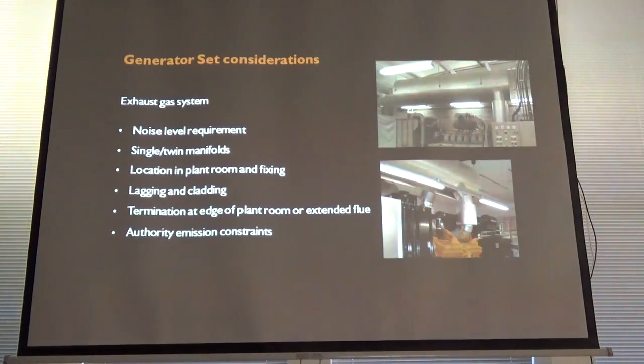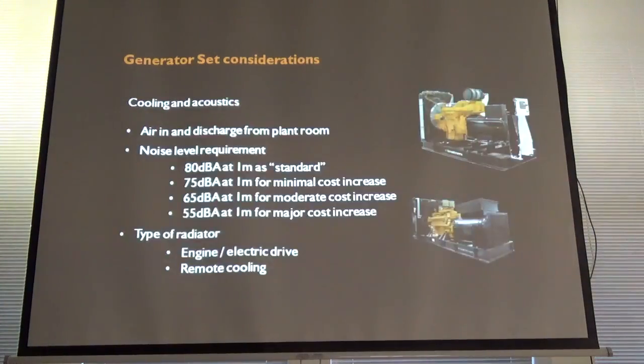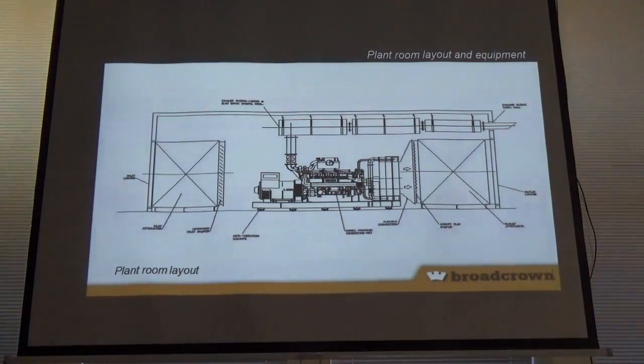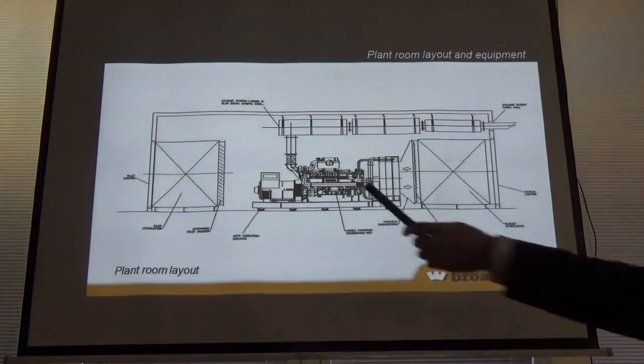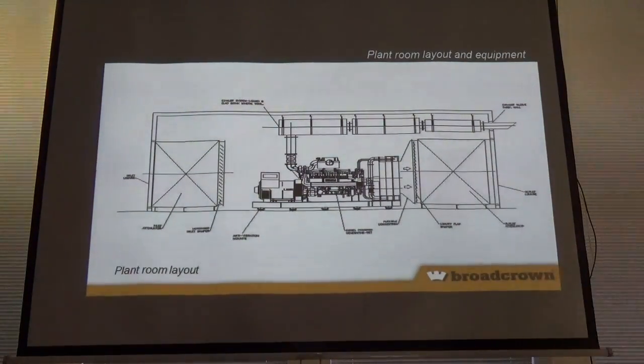You have skin temperature limits, sometimes touch, because sometimes they'll run through corridors and people can go up and touch them, and they'll have limits like 70-75 degrees centigrade, which then dictates the thickness of insulation you would need on that exhaust pipe itself as well, on the exhaust flue. So again, these can end up quite large diameters depending on the routes, turns, and back pressure limit that's left on the units. But in a plant room, you'll normally bang them above the silencer if you've got suitable head room, and actually even a simple one, as I showed you here, this arrangement. You have the exhaust silencer basically discharging out above here, and it's mixing with the discharge air, so it helps it disperse.